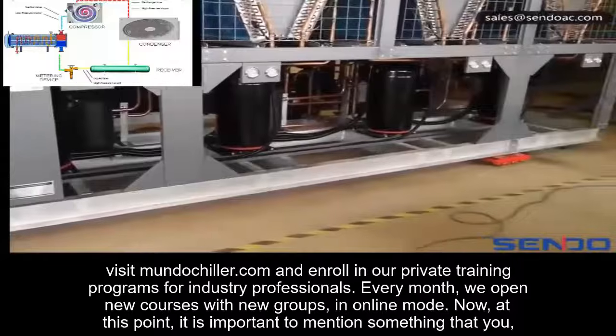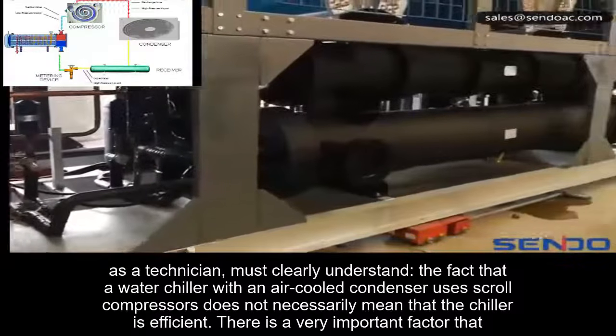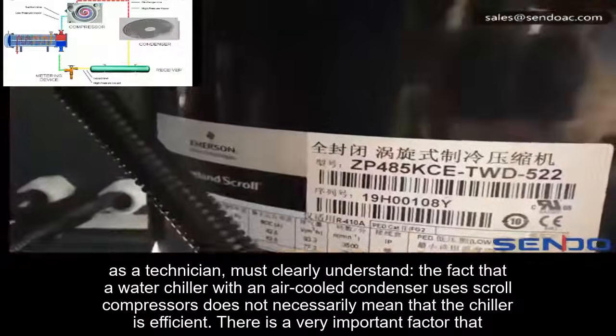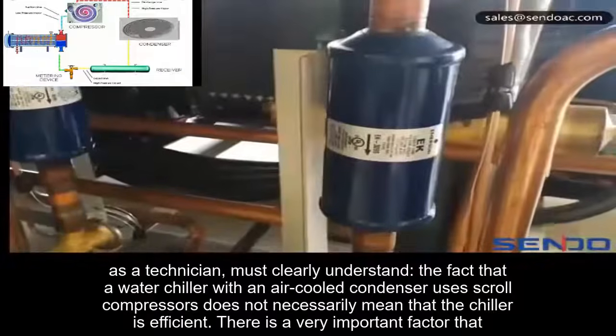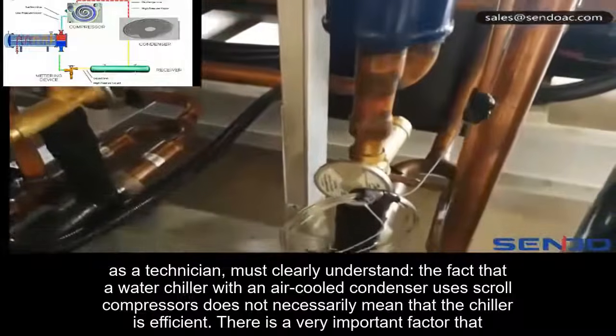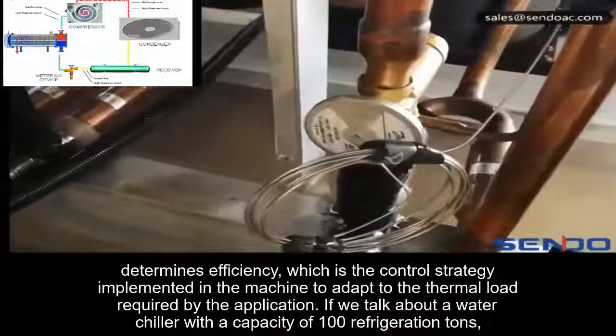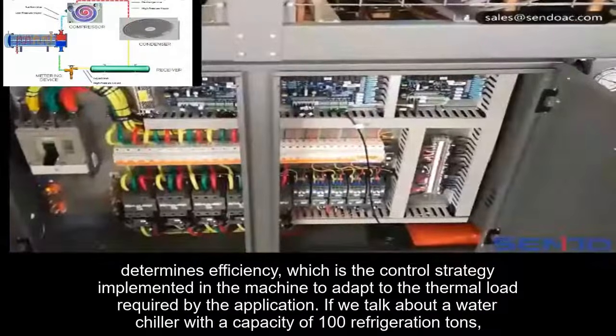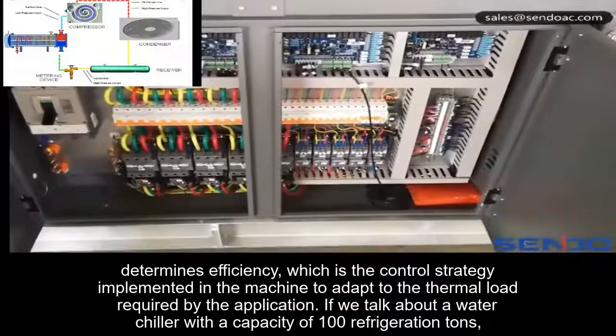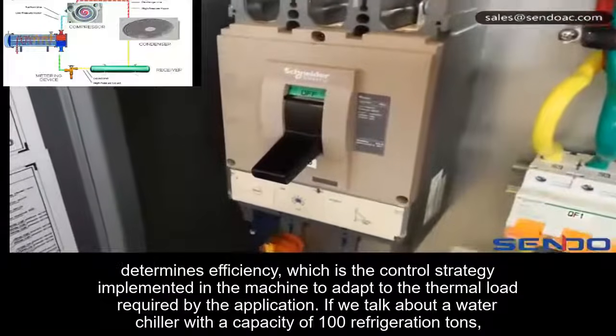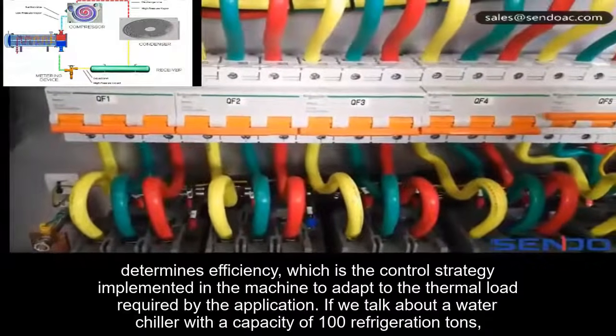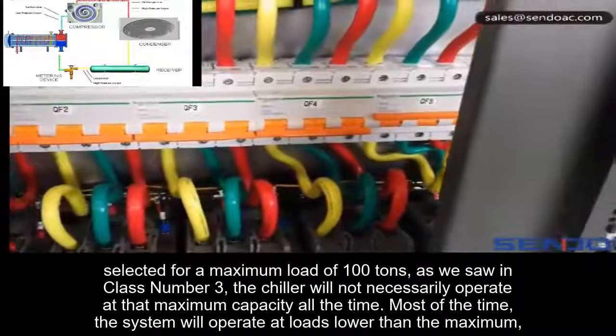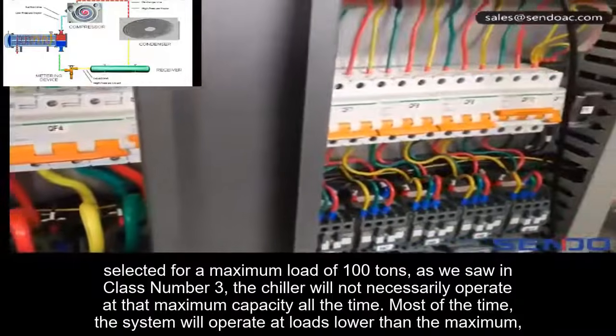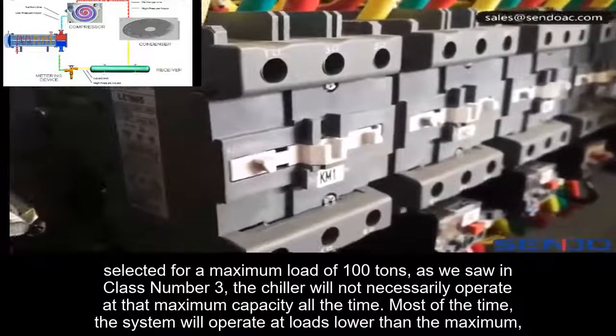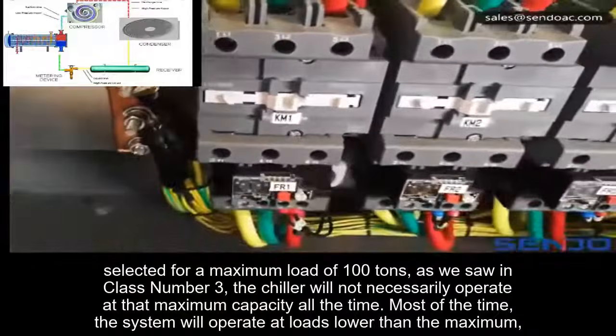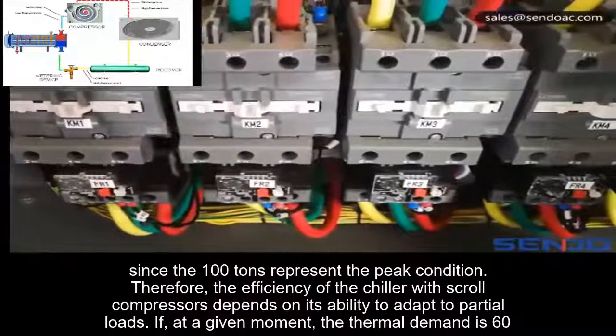Now, at this point, it is important to mention something that you, as a technician, must clearly understand. The fact that a water chiller with an air-cooled condenser uses scroll compressors does not necessarily mean that the chiller is efficient. There is a very important factor that determines efficiency, which is the control strategy implemented in the machine to adapt to the thermal load required by the application. If we talk about a water chiller with a capacity of 100 refrigeration tons, selected for a maximum load of 100 tons, as we saw in class number 3, the chiller will not necessarily operate at that maximum capacity all the time.